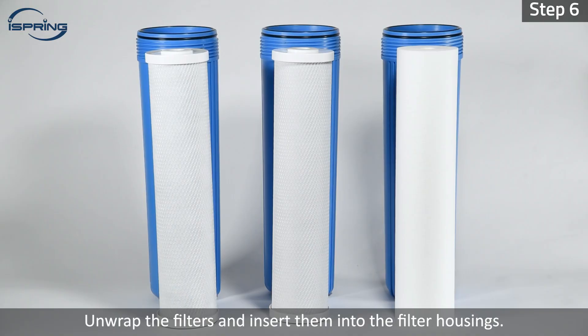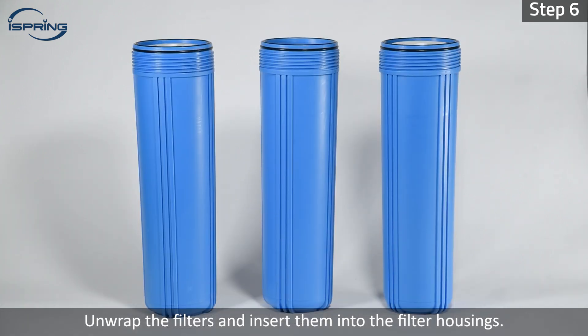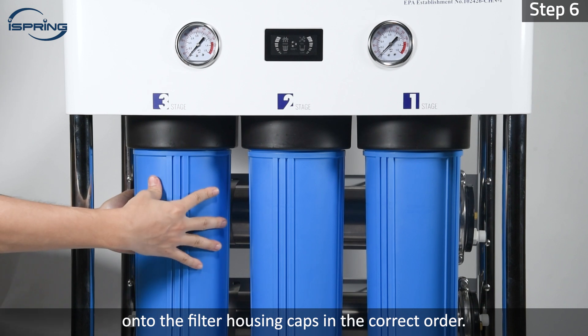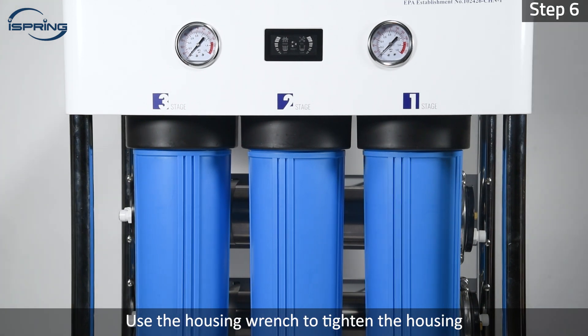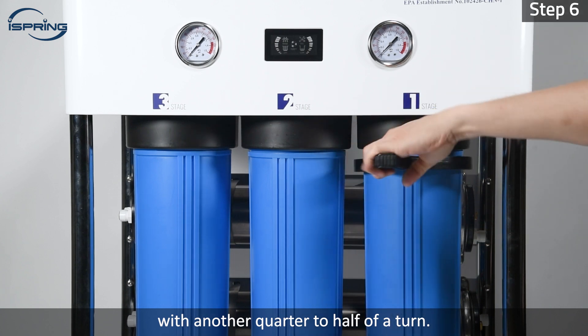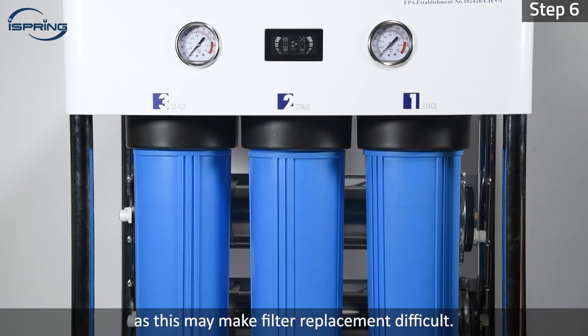Step 6: Unwrap the filters and insert them into the filter housings. Screw the filter housings clockwise onto the filter housing caps in the correct order. Use the housing wrench to tighten the housing with another quarter to half of a turn. Do not over tighten as this may make filter replacement difficult.